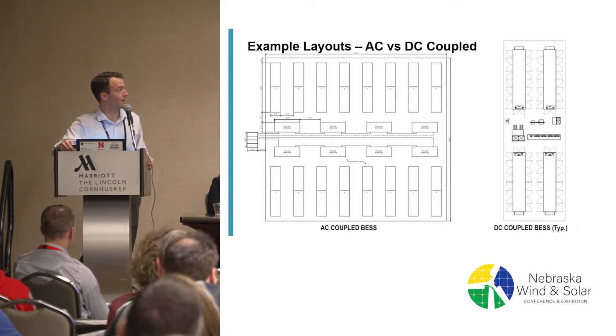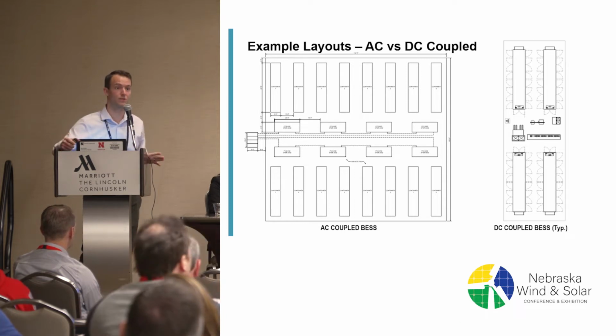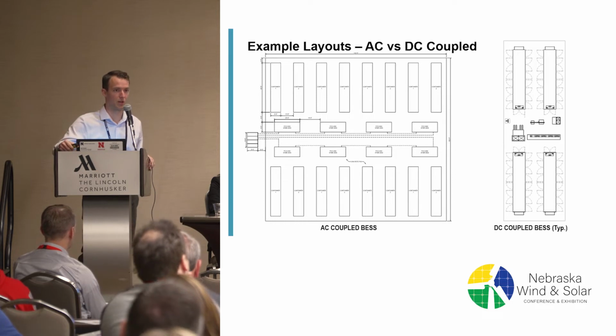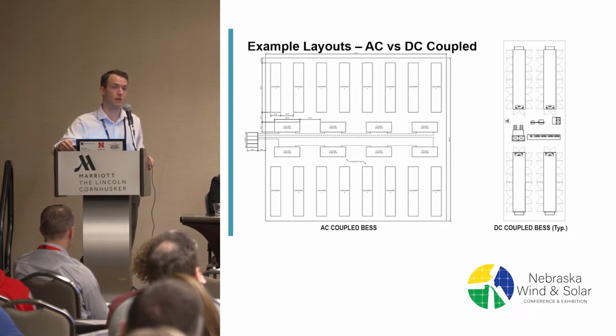The example on the left is an ideal situation. We're starting to see a lot more sites that we're trying to fit into interesting shapes, requiring more creative layouts. But generally it's a very rectangular approach - you place all the equipment as close as possible to your point of interconnection, within a substation if it's small, or outside the substation if it's paired with a solar array.